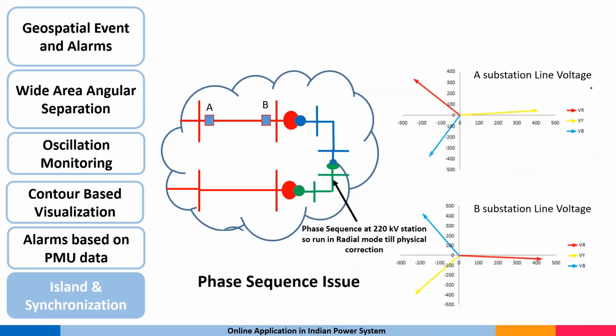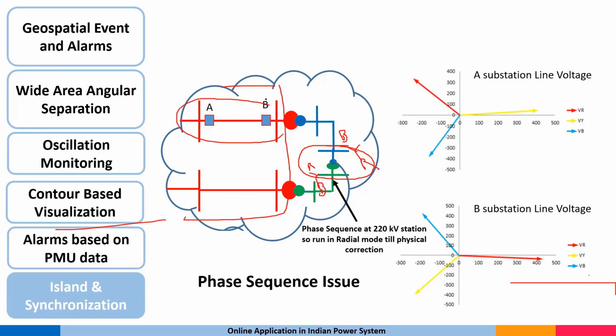Another problem is that there can be a phase sequence issue at the lower voltage level, because the distribution power system or the state power system evolved initially in a separate manner compared to the formation of the regional power system. So what we have seen is that there was a problem here. Across here, this is R Y B, and on this side the convention utilized is B Y R. However, this system is completely R Y B and R Y B, the 400 kV ISTS system. But at the lower voltage side, one side R Y B was there and another side B Y R was there. If you connect these in the same manner, R Y B to B Y R, there will certainly be a larger problem for the 400 kV, because the phase sequence will be opposite. Any kind of phase sequence opposition means we are connecting different phases with different phases, creating a short. So that will be a problem.